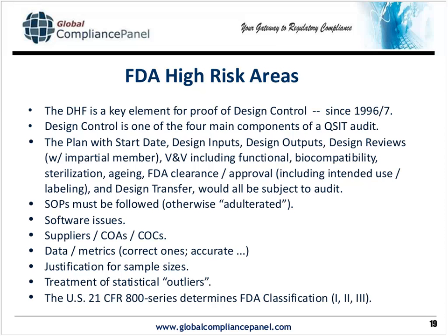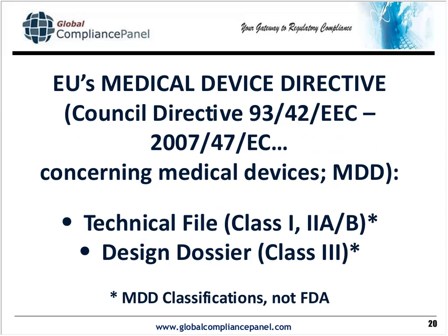If it's not classified, you have to talk to them. If it's not classified, more than likely you may have a PMA product where you have to do a long, involved, expensive process to get it to market with a lot of clinicals, not just a small amount. Just be aware of that difference. And again, if you're in R&D, you need to be aware of this as well. Slight differences can result in a classification change and a resulting cost-time element.